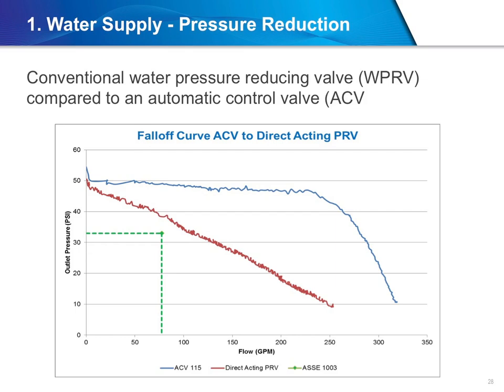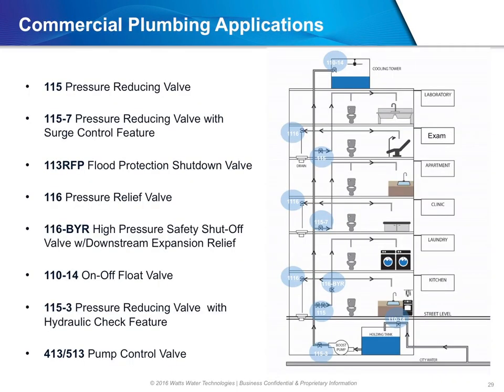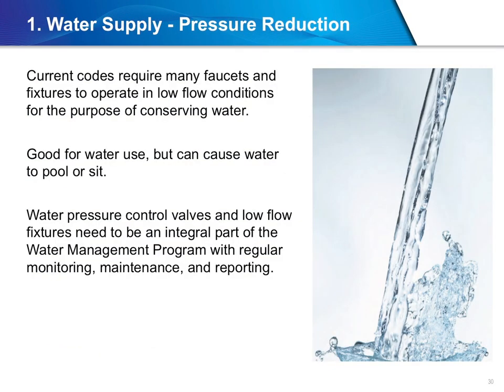The second option is to use an automatic control valve, or ACV, which provides the same function but is designed and constructed differently. The primary operating difference between an ACV and a WPRV is the flow rate in gallons per minute, or GPM, compared to the pressure in the system. Using a WPRV, the pressure will decrease as the flow increases. However, with an ACV, the pressure can remain fairly constant even as flow rates reach up to about 250 GPM. These are typical ACV applications in a commercial building. We show a high-rise, but you will also find ACVs in schools, hospitals, and other commercial buildings where a wide range of flows at a very consistent pressure are desired. One item related to flow rates is the current code requirement for many faucets and fixtures to operate in low flow conditions for the purpose of conserving water.